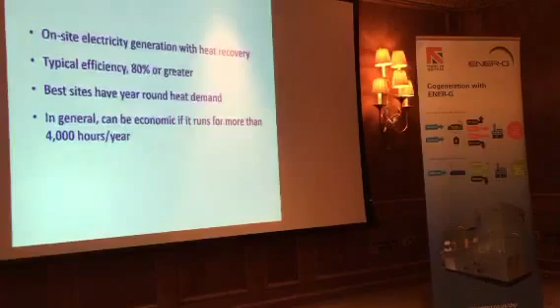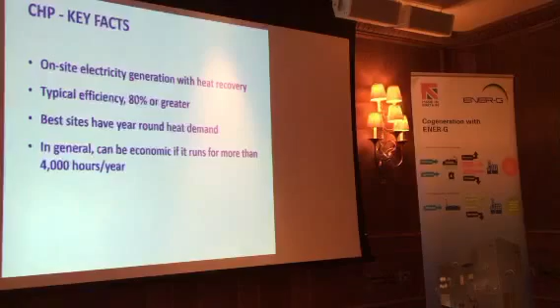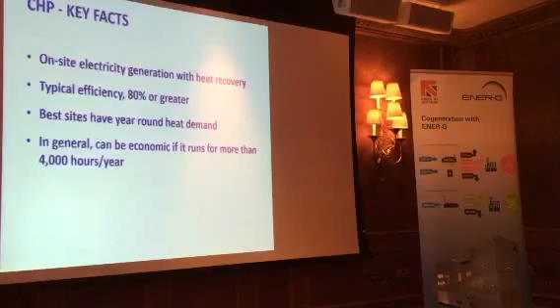The idea here is you need enough heat to keep the engine running as much as you can. If you can run it 8,760 hours a year, you'll get a fantastic return on investment. But typically, if you can get into the 5,000 hours per year area, then you're into an economic CHP situation. If you tried to put it in a school, it would probably run 1,000 hours. It would work, but it wouldn't give you the return on investment.